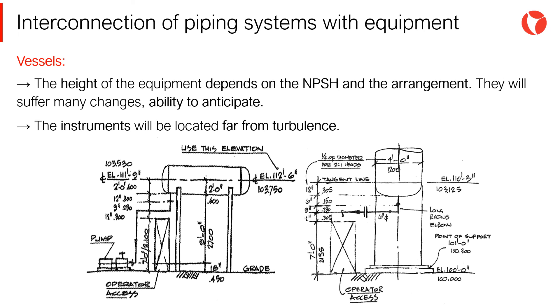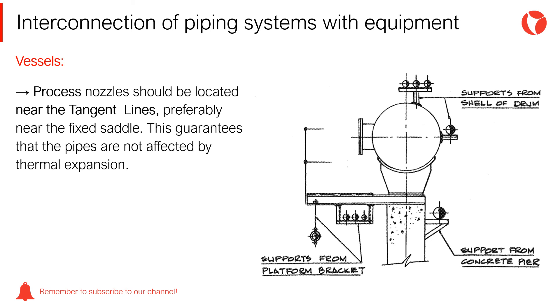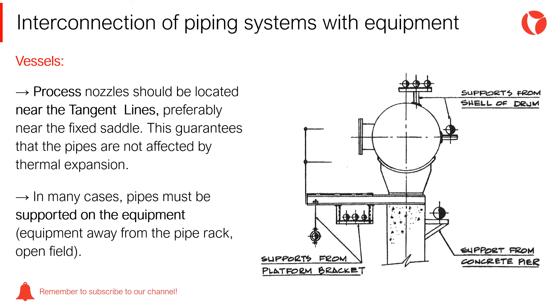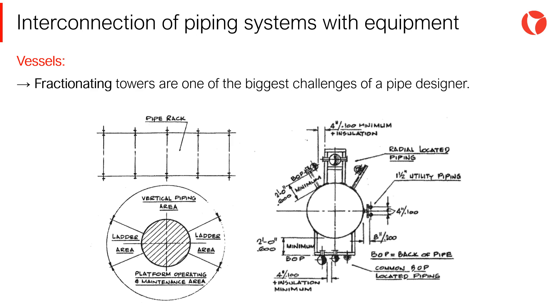Instruments will be located far from turbulence. Process nozzles should be located near the tangent lines of the equipment, preferably near the fixed saddle — this ensures that the pipes are not affected by thermal expansion. In many cases, pipes must be supported on the equipment, for example when the equipment is away from the pipe rack or installed in open field. Vertical equipment such as fractionating towers are generally more complex when it comes to piping design. Fractionating towers represent one of the greatest challenges for a piping designer, mainly due to the process requirements, the number of pipes and nozzles, and the limited space in the equipment.